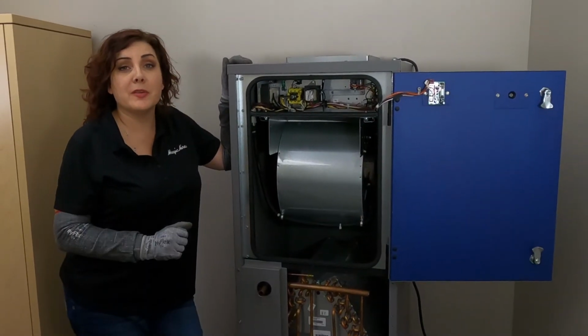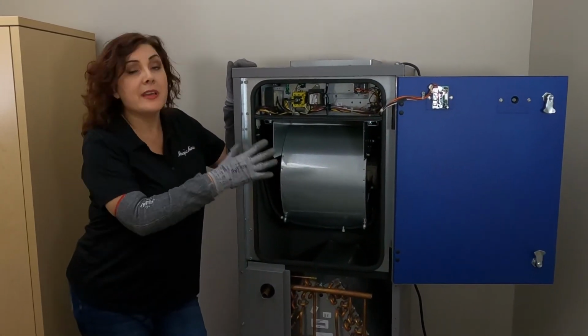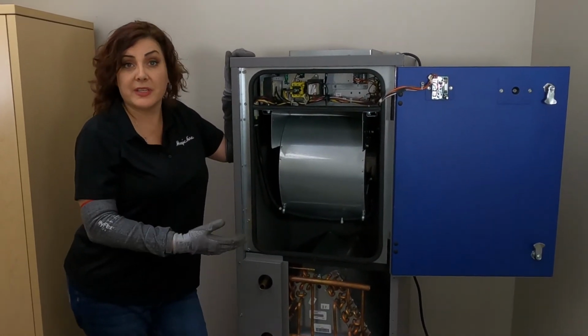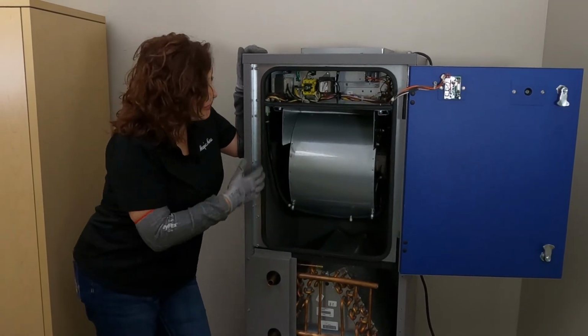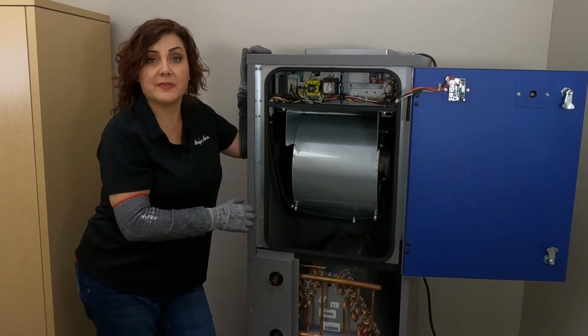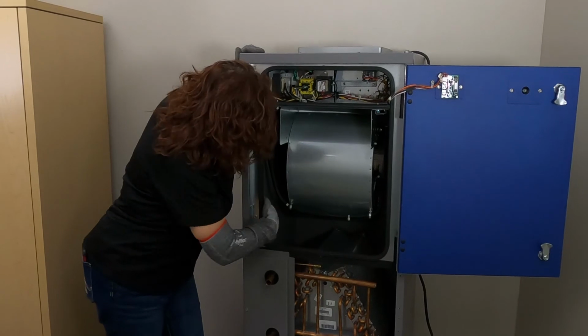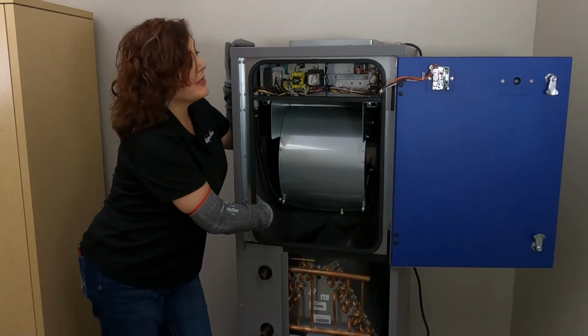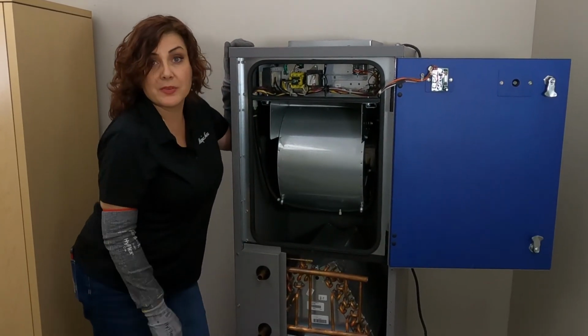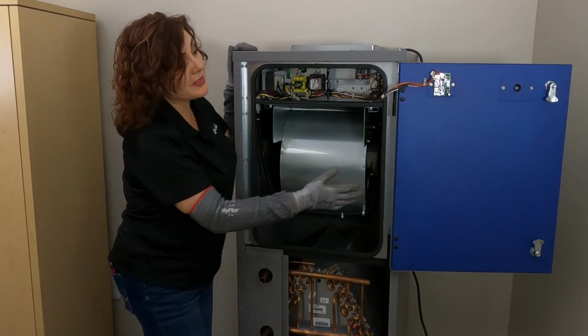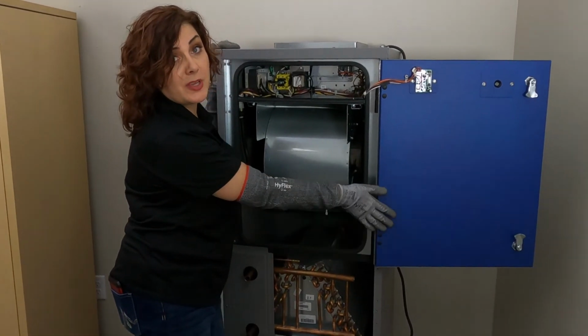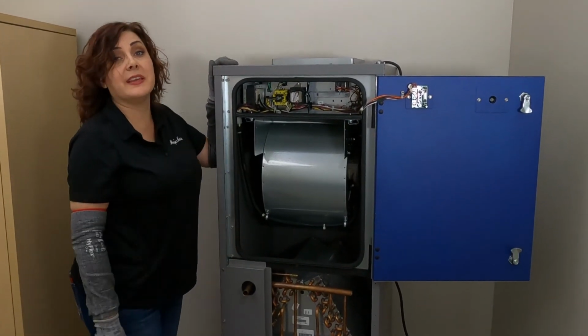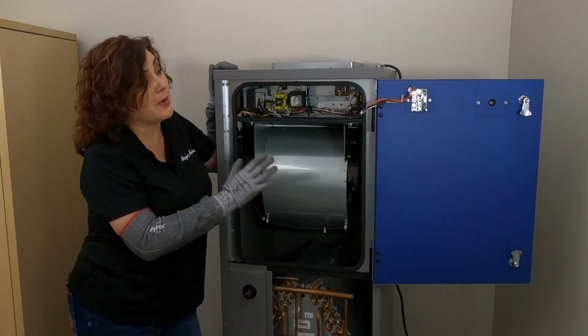The last item on your preventive maintenance list, every time you do servicing on the unit that involves any liquids or brushing out the blower, you're going to want to wipe out the inside of the unit. So just wipe the inside surfaces of this double wall unit. It's very easy to wipe off with a cloth. You can use a mild detergent, especially if you have an antimicrobial coating. You're going to want to carefully take care of that and not do anything to mar that surface.